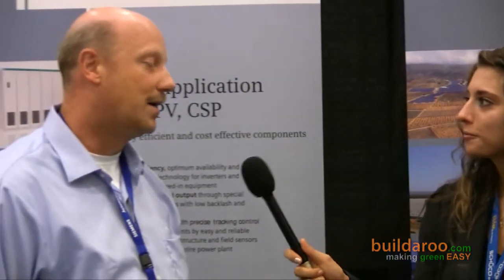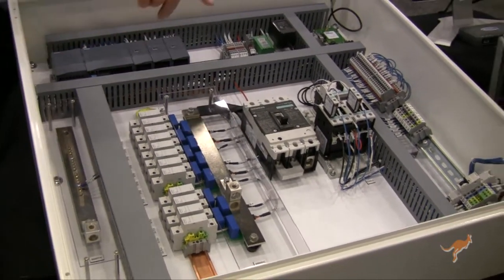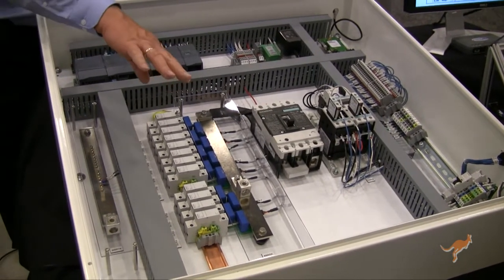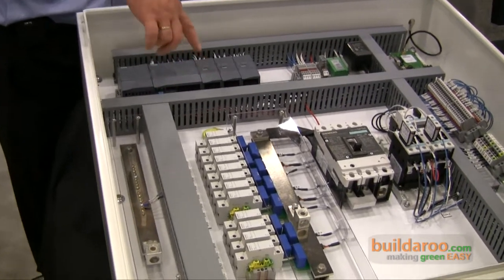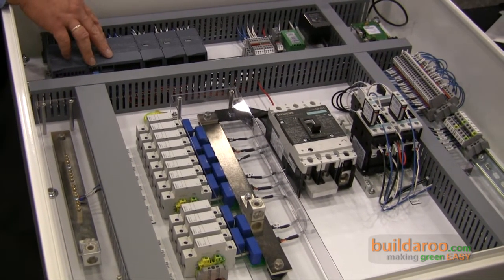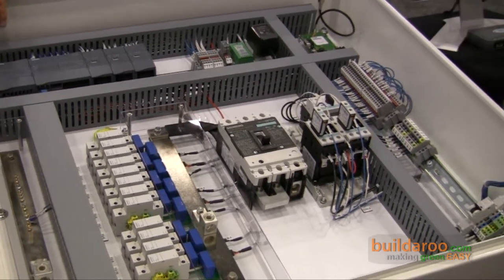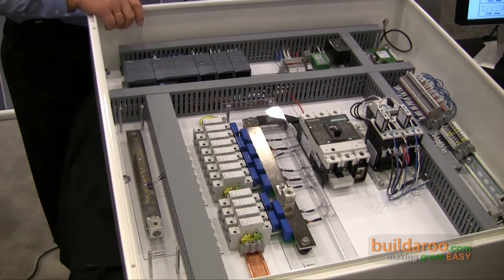Is there anything you'd like to add about Siemens — any upcoming projects, events, or new product lines? We are planning to be at the Solar Show in Anaheim in October. We will present our inverter and also this smart combiner box. It is a standard solar combiner box which integrates the combining part — where you have strings coming in from the solar field and combine them to one current back to the inverter — and it also has a PLC, our SIMATIC S7-1200, that can read and monitor the string current and bus bar voltage. With the PLC, it also has the capability to run a tracking algorithm that positions the PV panels toward the sun, all combined in one box with a wireless interface to a host PC. That's our latest invention.